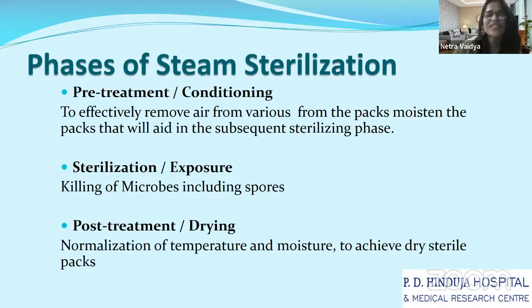So the phases of steam sterilization are basically, first, a pre-treatment wherein you remove all air from the chamber and from the packs. Then you moisten the pack so that it facilitates the sterilization. Then there is the sterilization or exposure period, which again depends on various factors: what are you going to sterilize, and how much time you need.